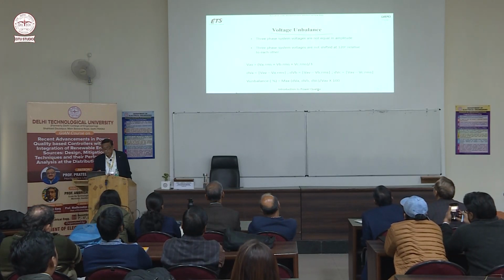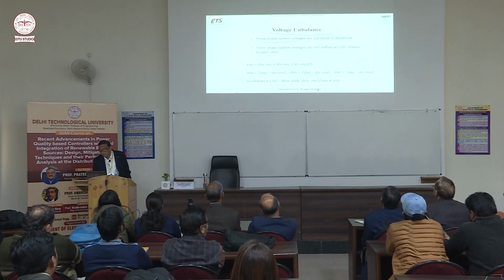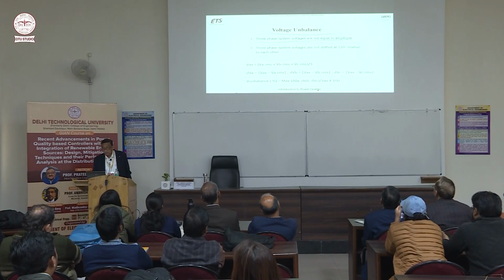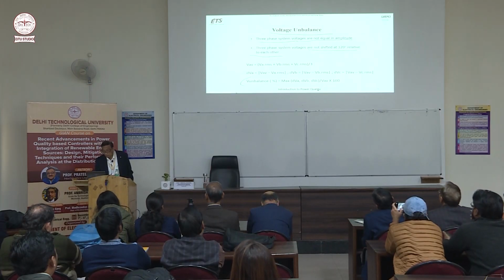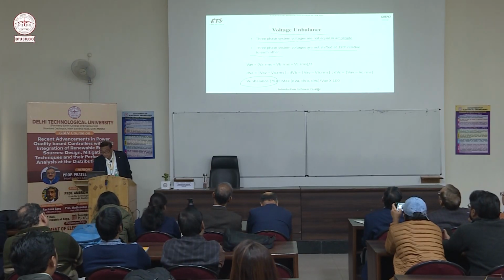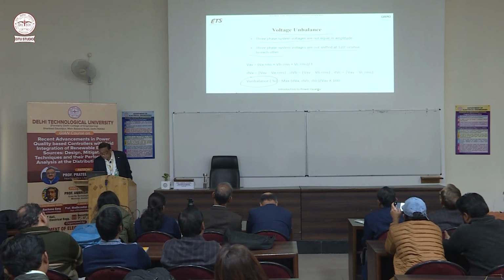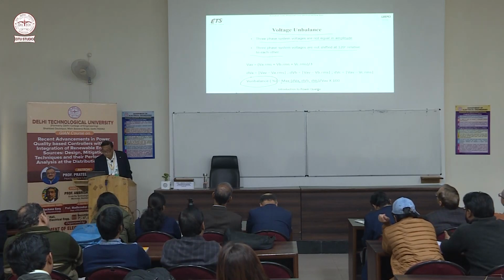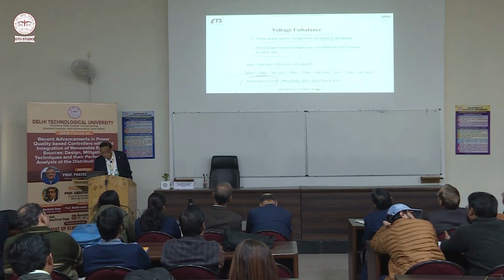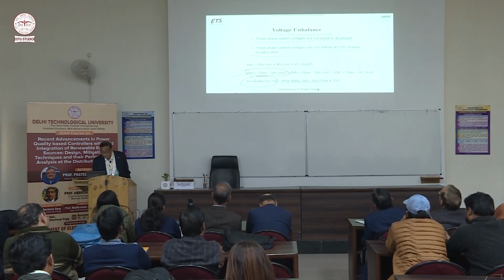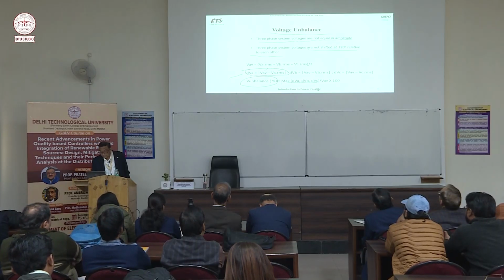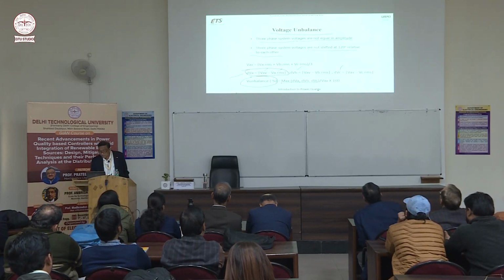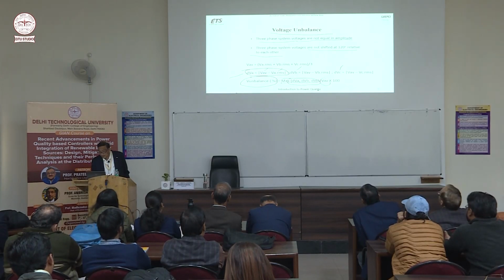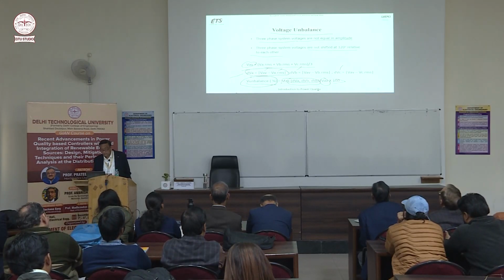Voltage unbalance. Three-phase system voltages are not equal in amplitude, or they are not shifted by 120 degrees relative to each other. So how do you calculate the voltage unbalance in percentage? It is the maximum deviation: the deviation in phase A voltage, the difference between the average voltage and VA RMS, or phase B, or phase C. You see which one is maximum, divide it by the average voltage and multiply by 100, and it will give you the voltage unbalance in percentage.